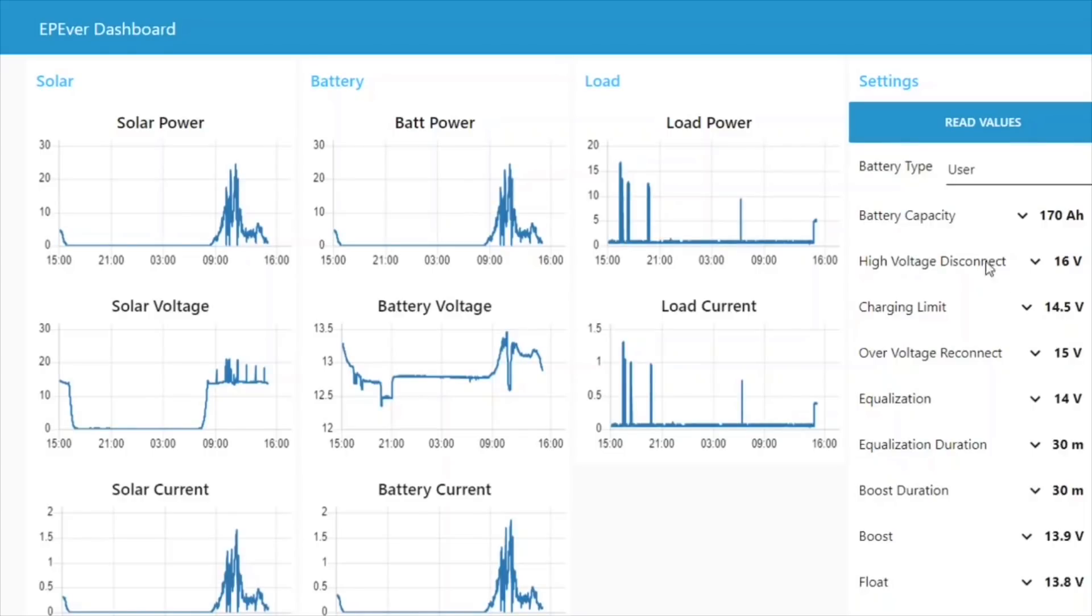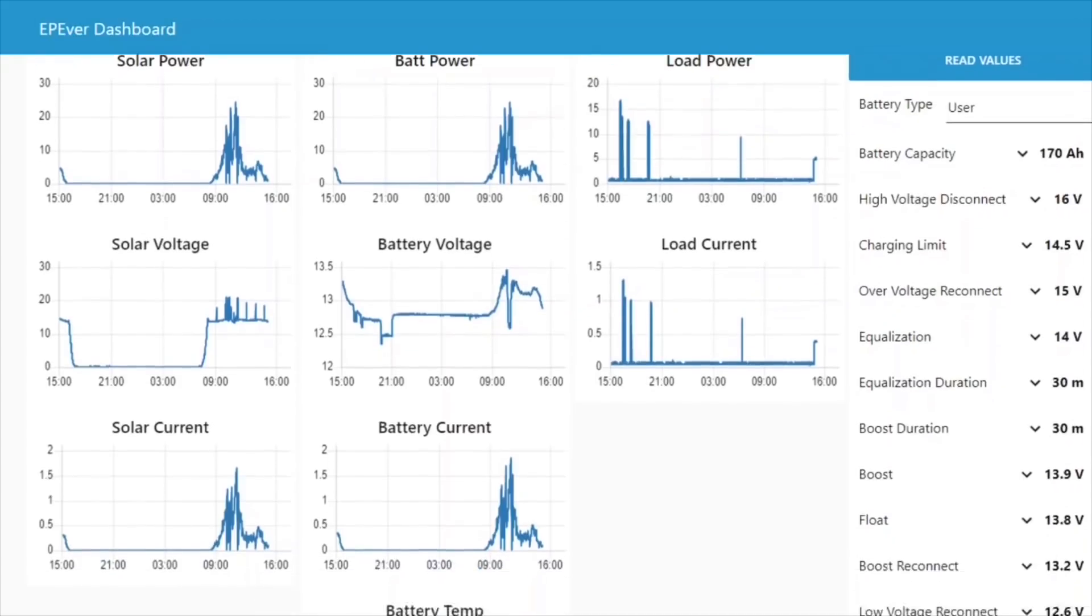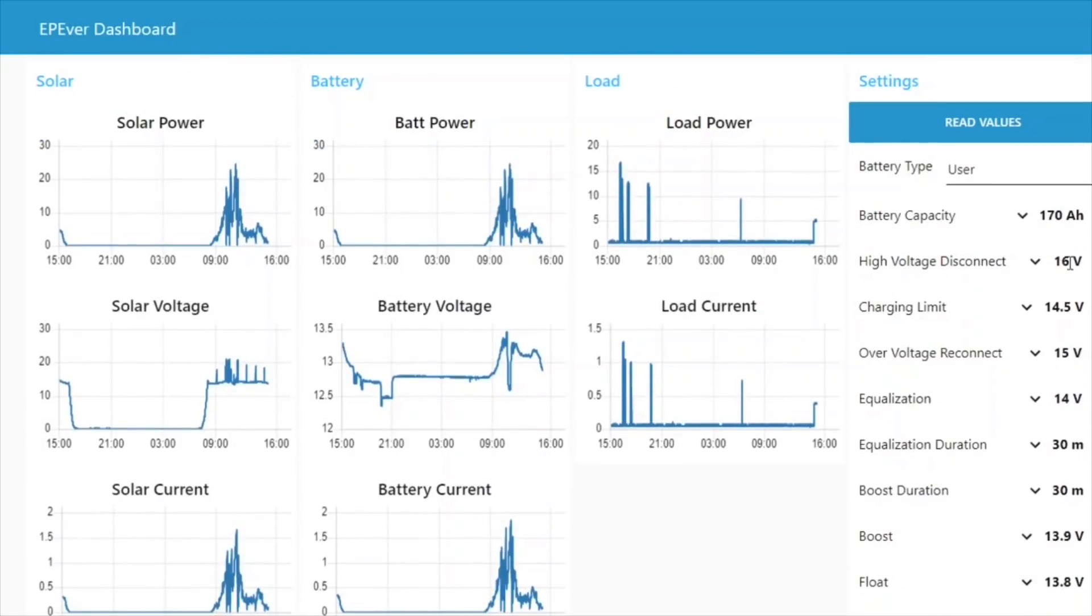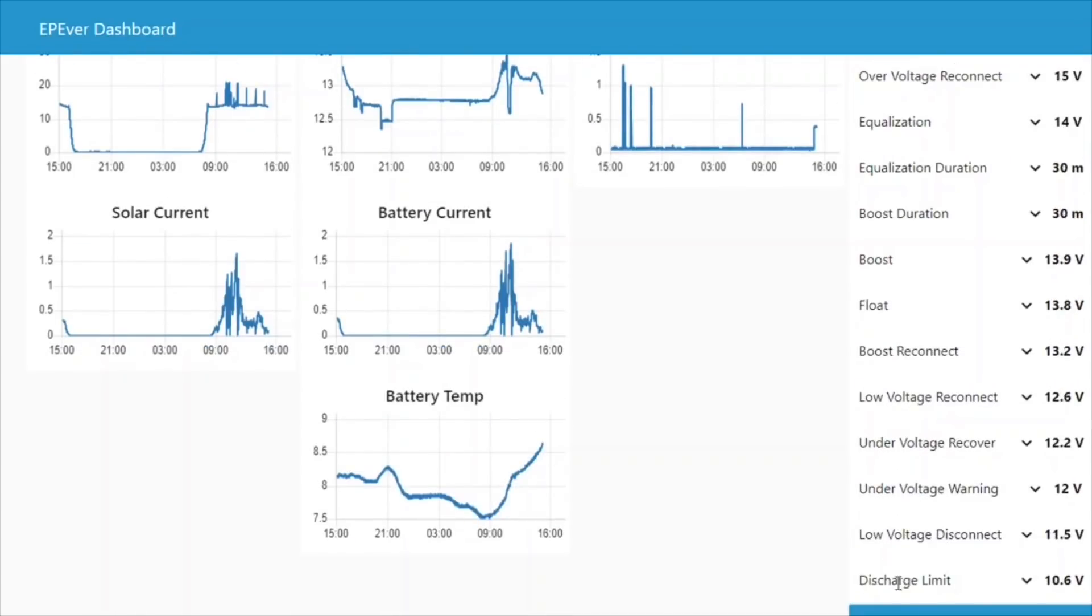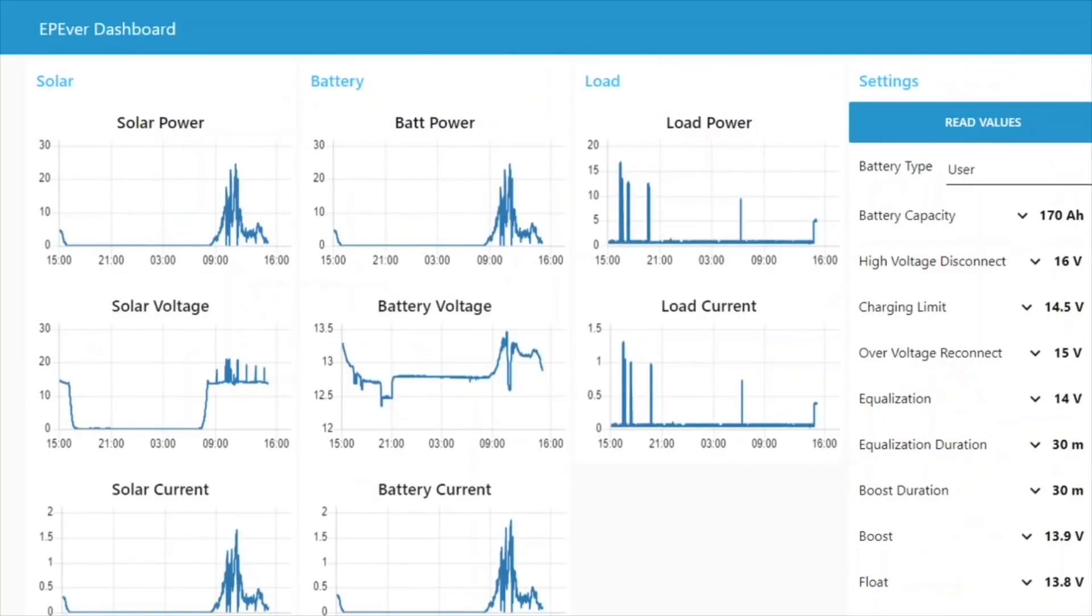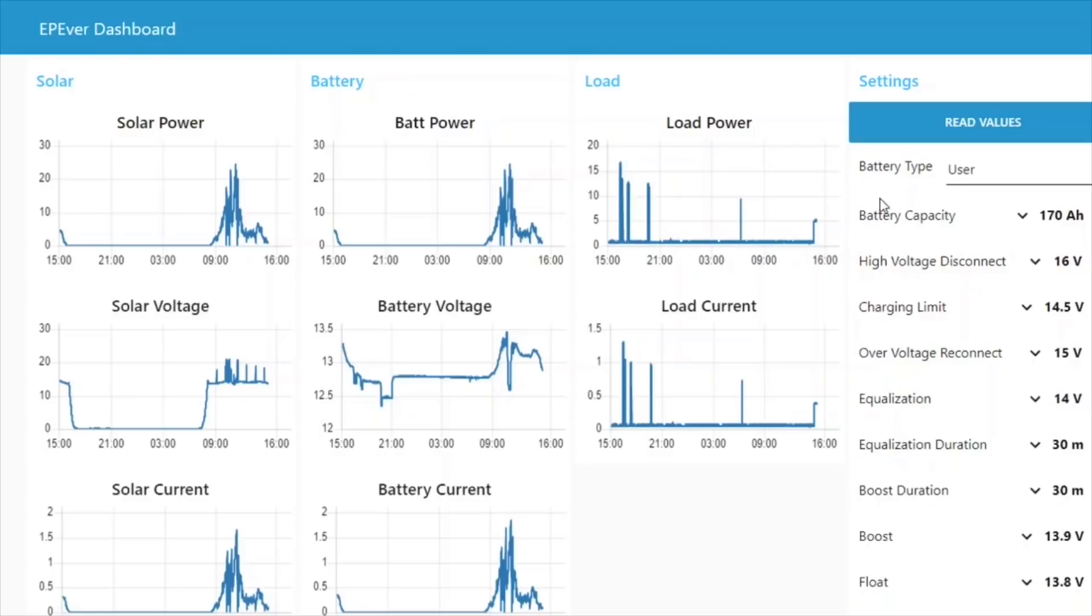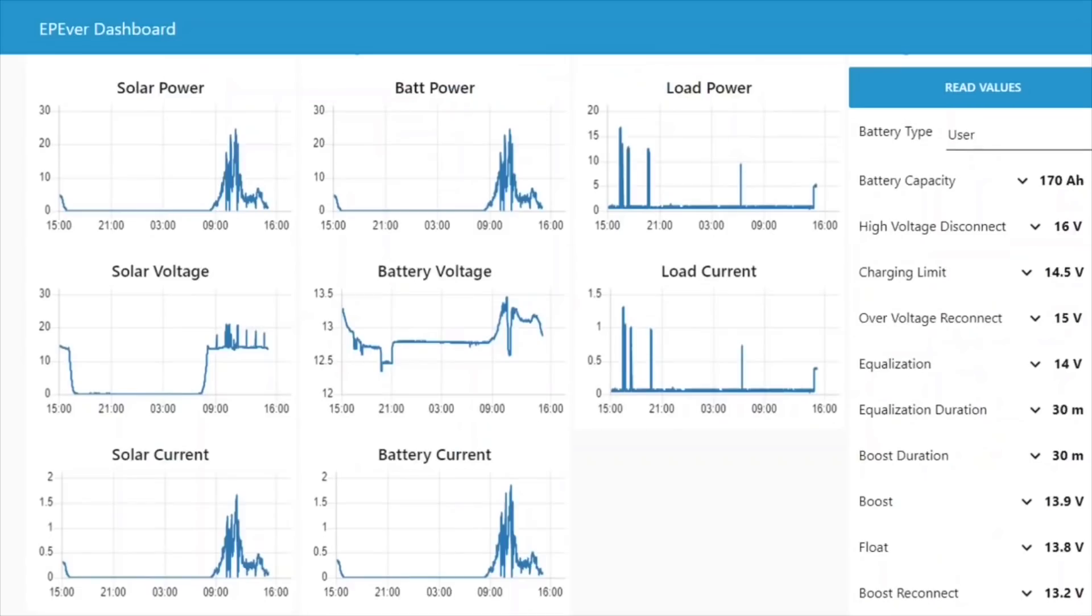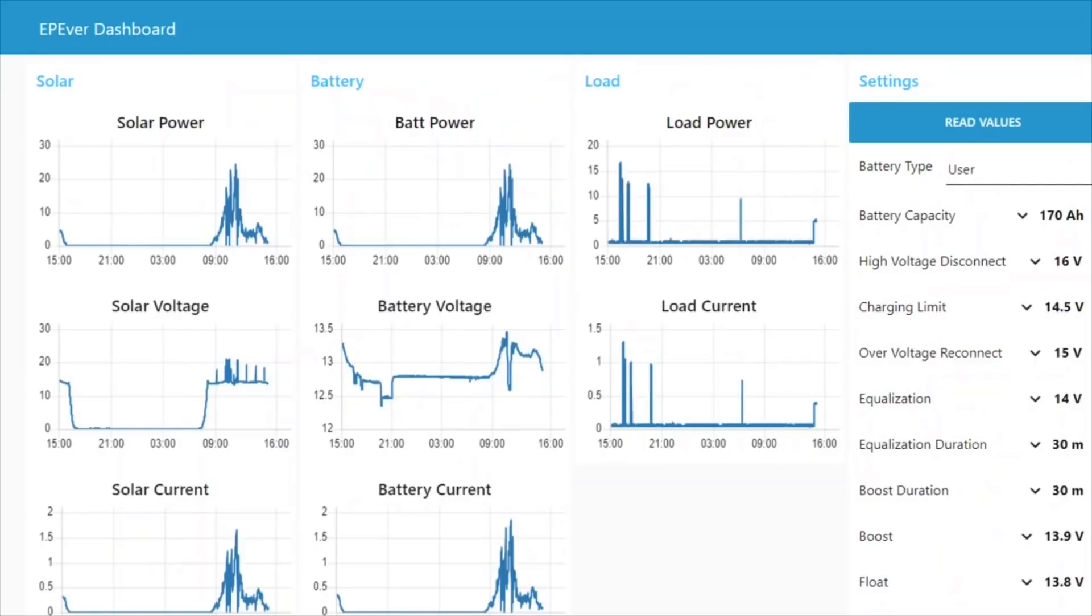It's worth noting that these are all in a hierarchy order, you can't have the charging limit set above the high voltage disconnect, for example. So the highest voltages are set at the top, and the lowest voltages are set at the bottom, the discharge limit can't be higher than the low voltage disconnect limit, for example. So I think this is possibly the only EPEver dashboard out there. There's not the official Windows client that you are able to actually change all the values on the solar charge controller. So I'm pretty pleased with that.